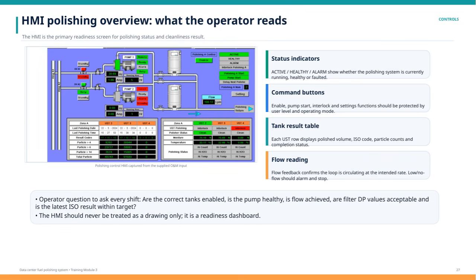Operators are encouraged to ask themselves key questions each shift. Are the correct tanks enabled? Is the pump functioning properly? Is the flow rate being achieved? Are filter differential pressures within acceptable limits? And finally, is the latest ISO cleanliness result within the target range? Importantly, the HMI is much more than just a visual schematic or drawing. It's a dynamic readiness dashboard that provides essential, actionable information to keep the fuel polishing system running safely and effectively.